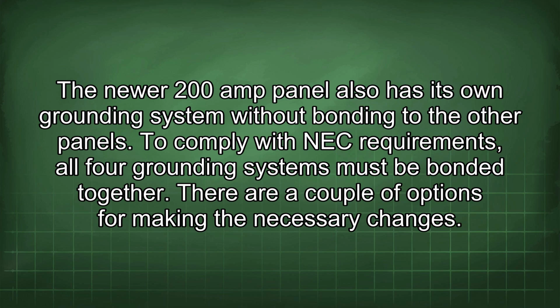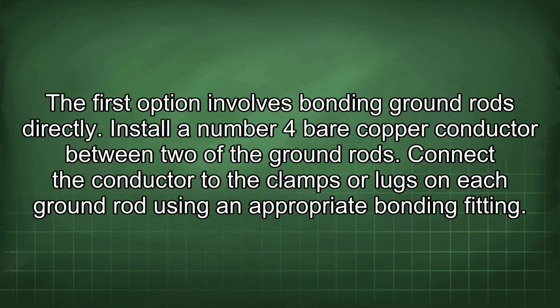To comply with NEC requirements, all four grounding systems must be bonded together. There are a couple of options for making the necessary changes. The first option involves bonding ground rods directly. Install a number 4 bare copper conductor between two of the ground rods. Connect the conductor to the clamps or lugs on each ground rod using an appropriate bonding fitting.